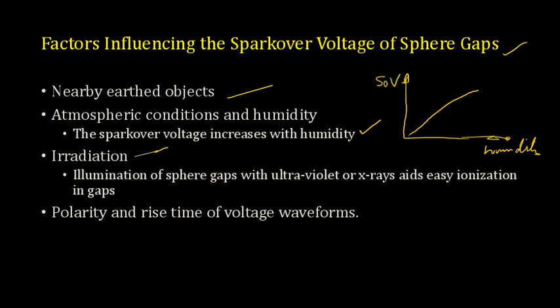Irradiation affects the spark over voltage. That is, we are illuminating the sphere gap with ultraviolet or X-rays. That helps in the ionization of the air gap. So if you are doing that, the spark over voltage will reduce. You are able to identify lower voltage if you are making use of irradiation.